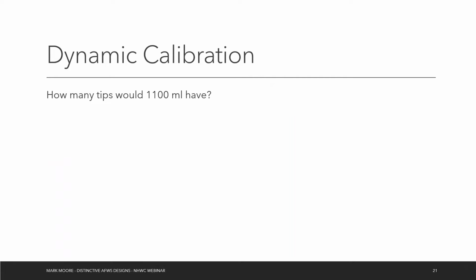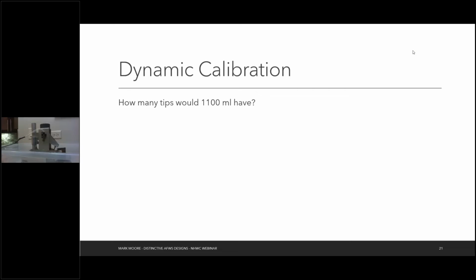So a dynamic calibration. The dynamic calibration is going to say, okay, rather than just do one tip, let's do multiple tips. And the question immediately asks here on the slide of how many tips would 1,100 milliliters have? And there's a reason that we're using that number. The reason is because we're going to be doing it with an Nalgene. And this Nalgene fills up to 1,000 milliliters, but all the way to the top is actually 1,100 milliliters.